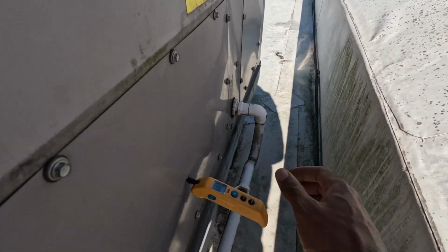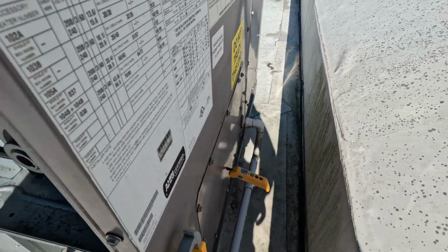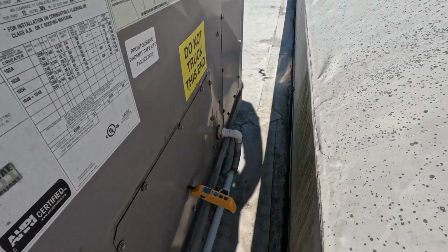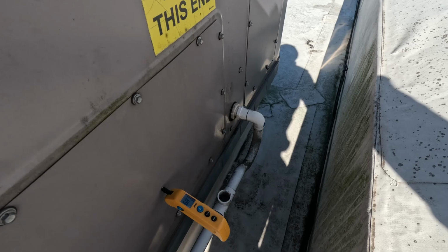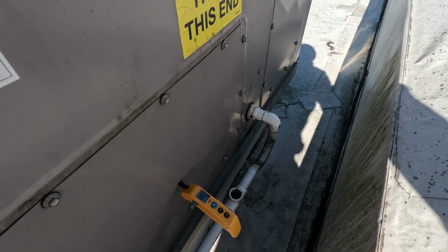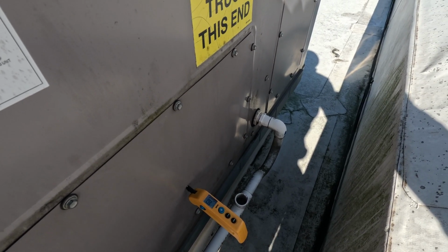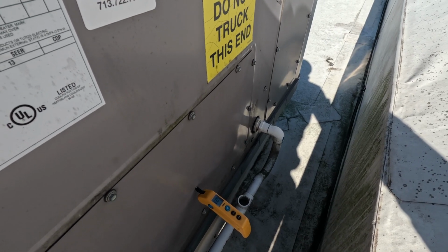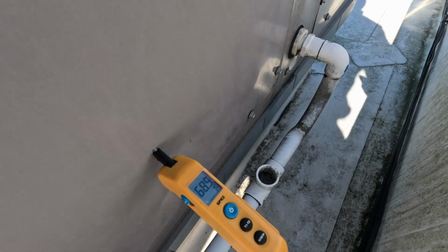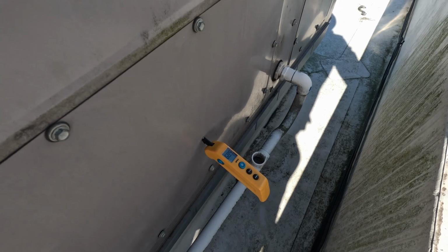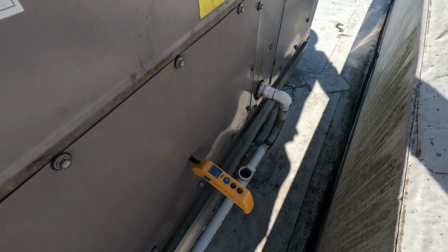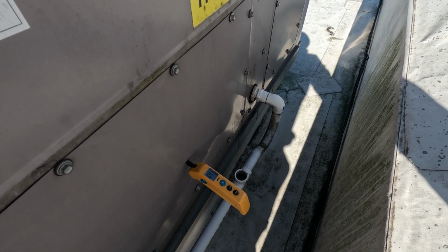We're gonna make sure it doesn't go above 200 degrees with the heater on. The instructions say run it through 5 cycles to make sure it doesn't exceed 200 degrees and damage the cell on the air scrubber.